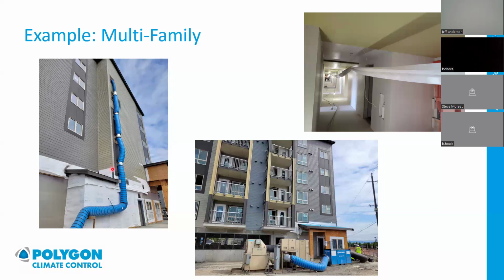This is a multifamily building, obviously. They've just taken out a window here in this hallway and popped the ductwork in. So you've got all these levels here. Each of the hallways has this lay flat poly. This one's actually deflated. They had a dust concern at the time, so they just tied it off with some twine. But normally this poly here would be inflated, a nice round, super buoyant, super lightweight poly duct. It's perforated. It just sprays that dry air all over the building. Because all the air is touching, it's going to distribute fairly well without having to have the ductwork run into every little nook and cranny.